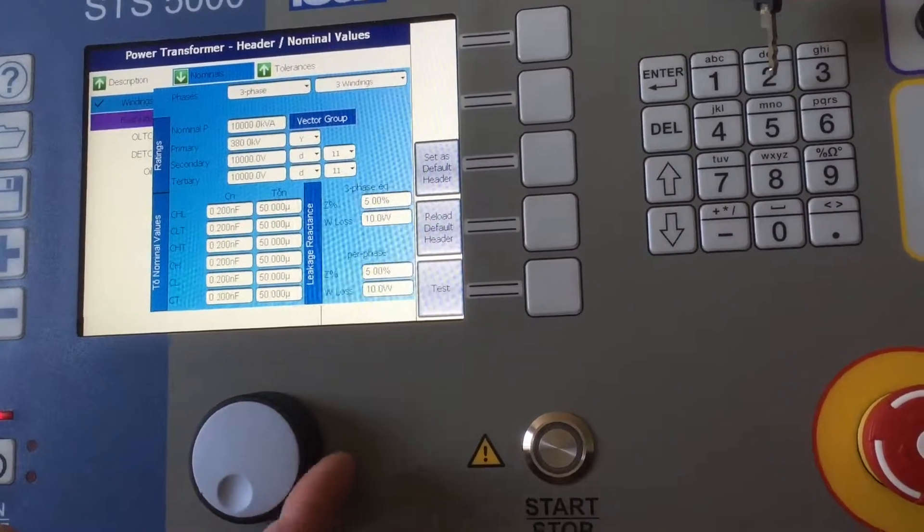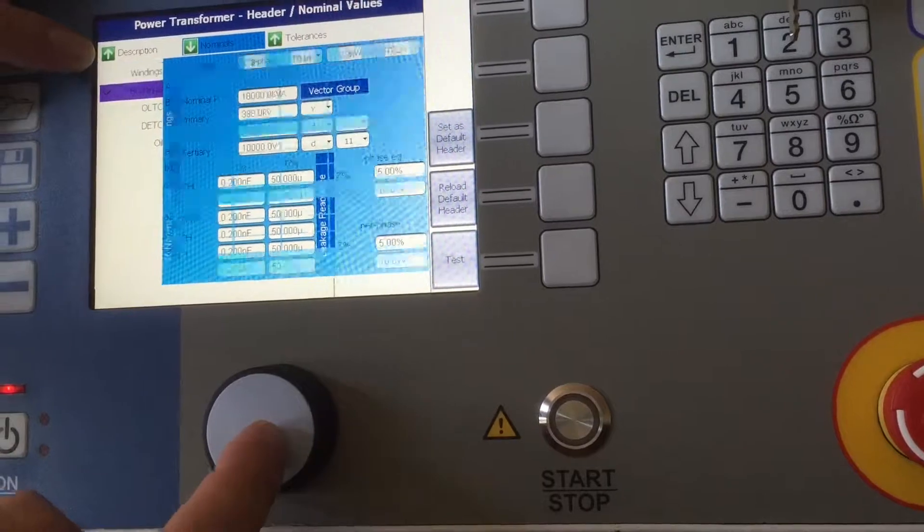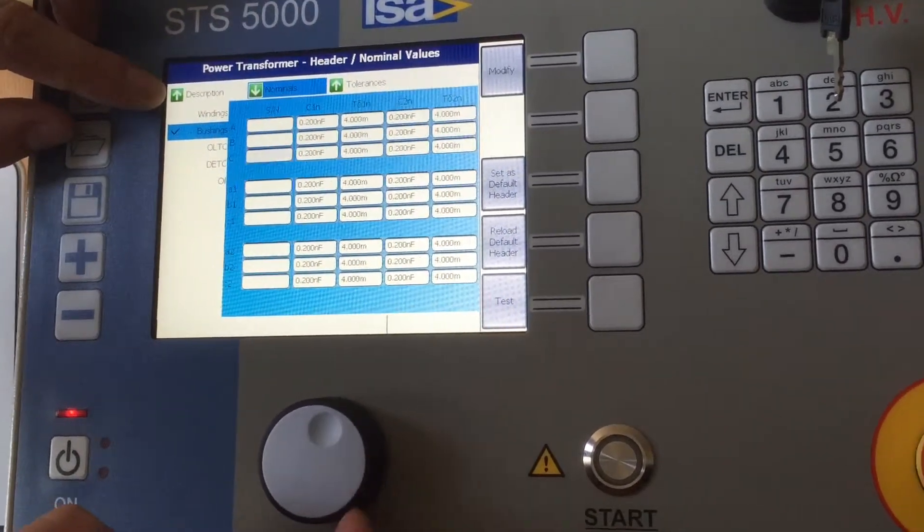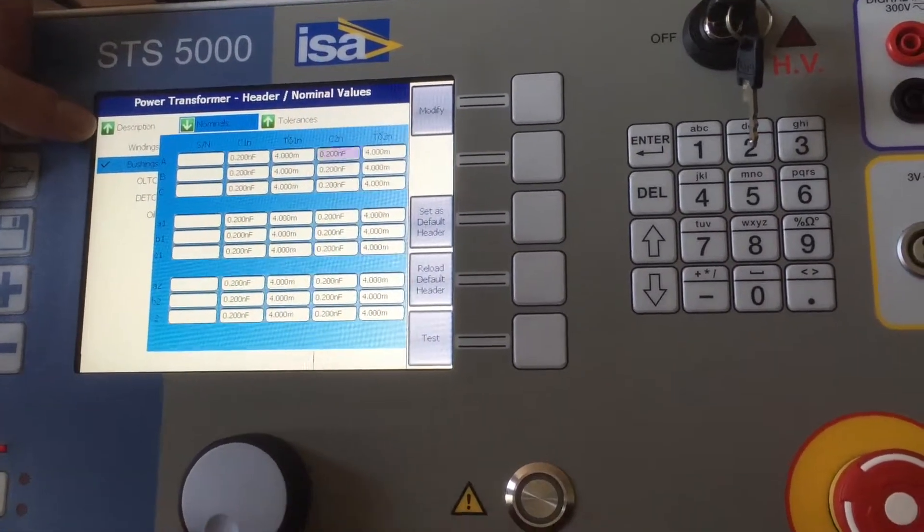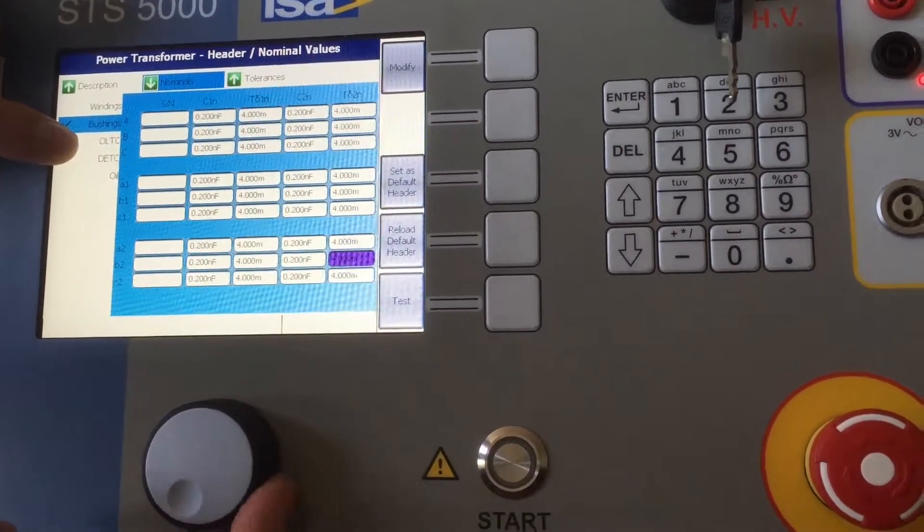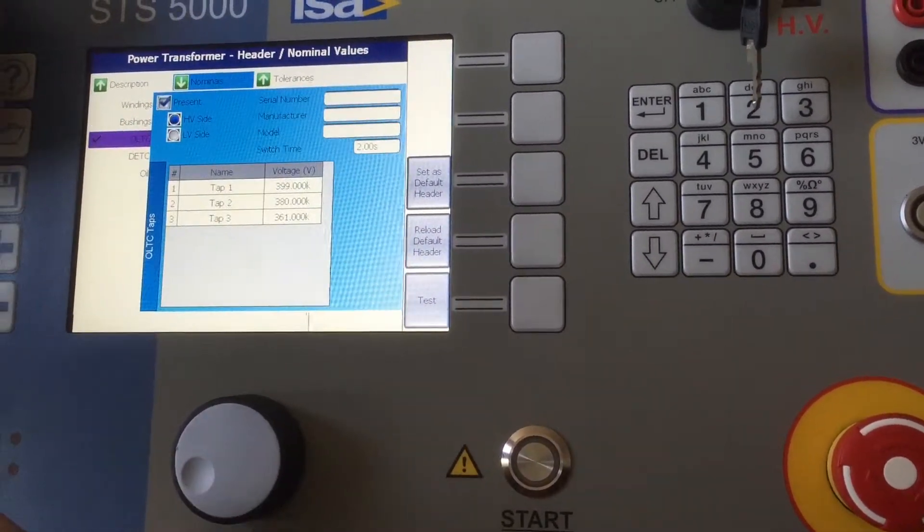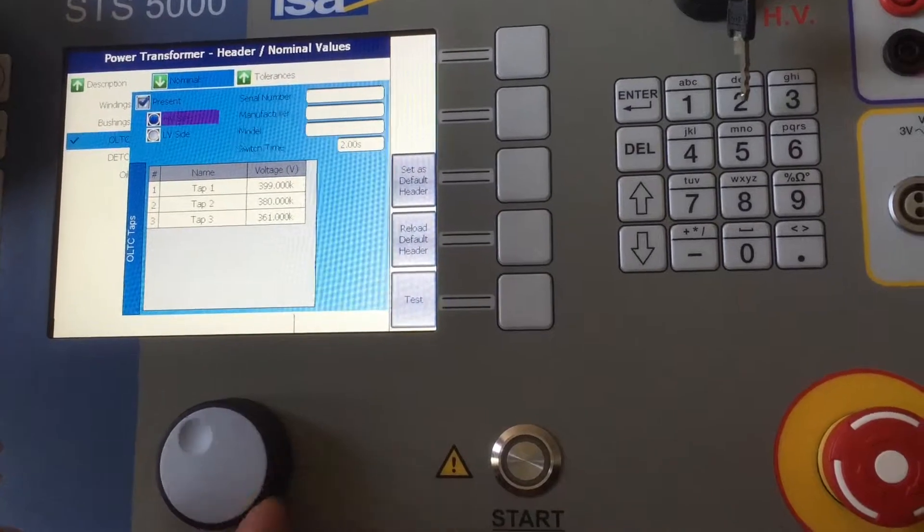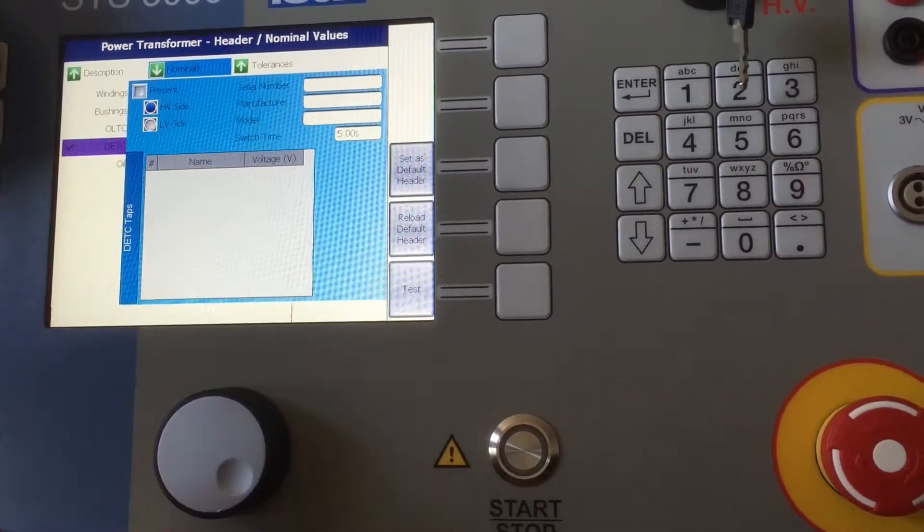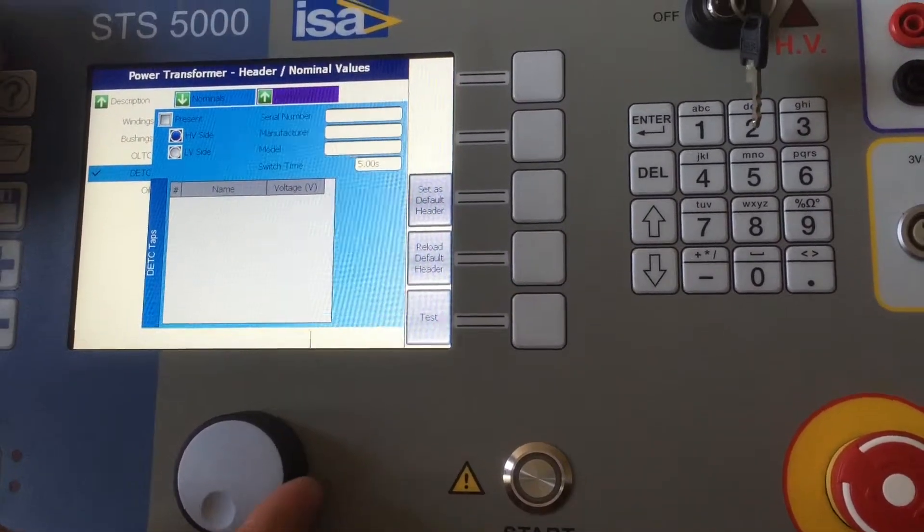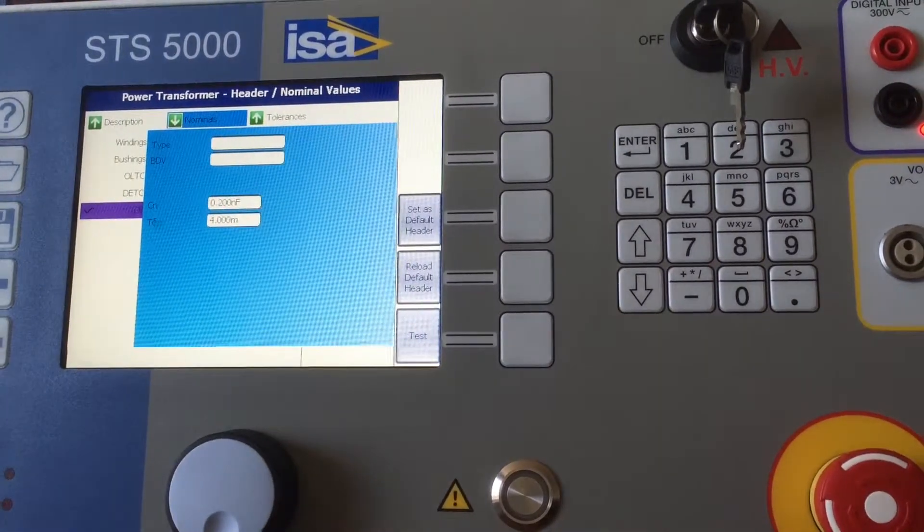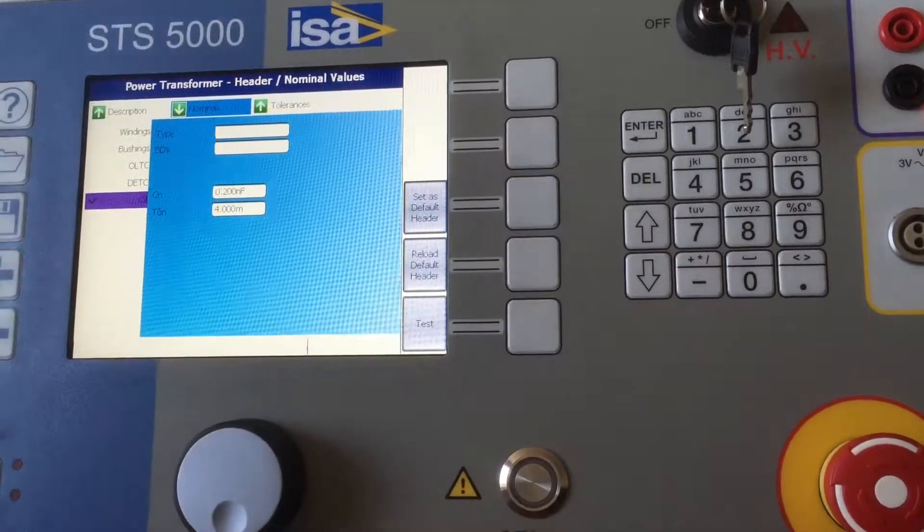After that you can do this not only for the windings but also for the bushings, and after that it would be good to also define if there is an onload tap changer or de-energized tap changer. There is also an option to test for tan delta which is a power factor test to oil.